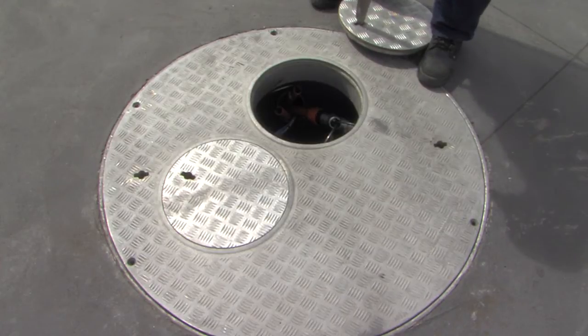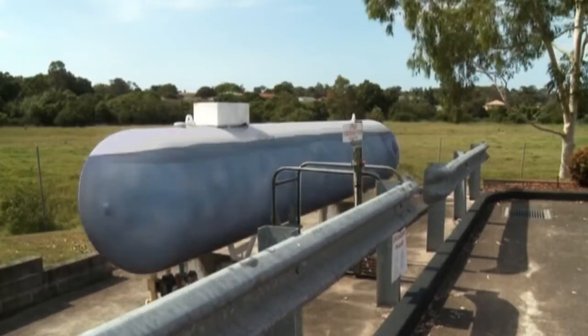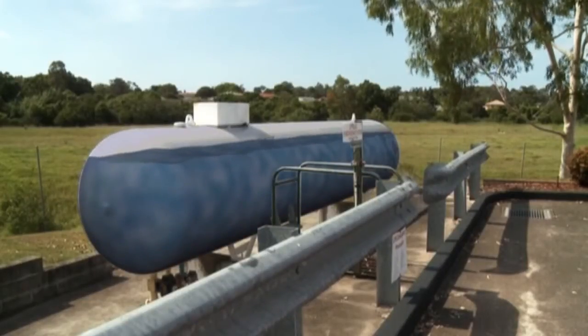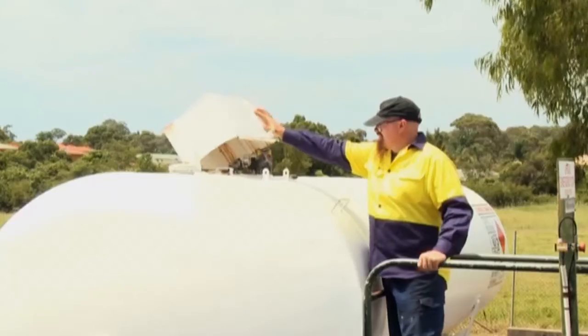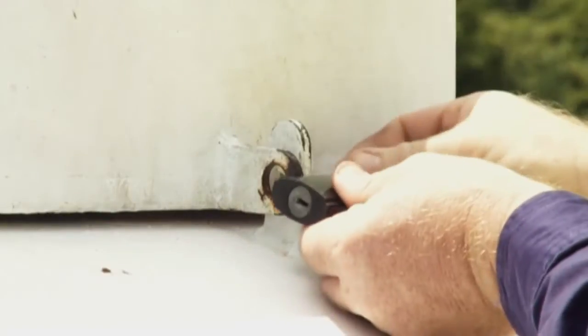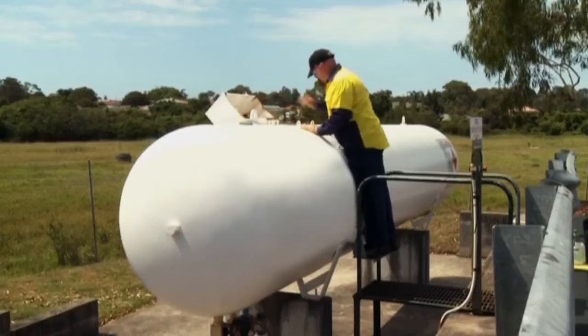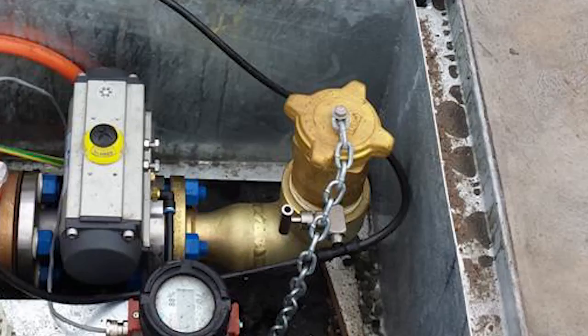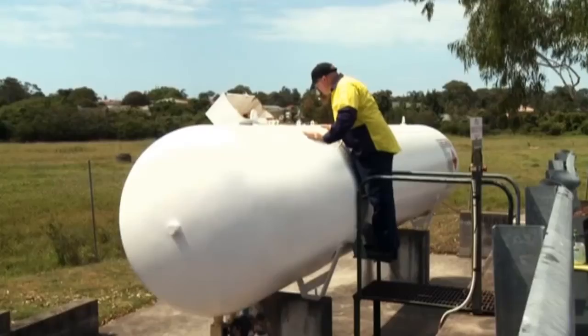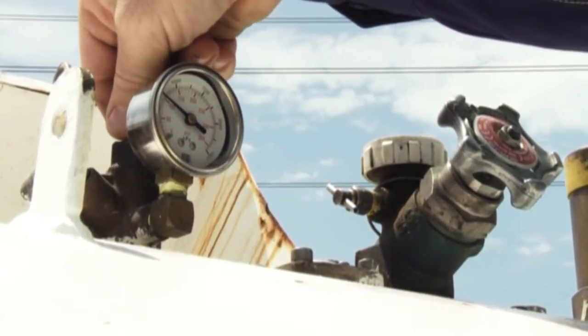System checks should include but are not limited to the following. Level gauges, pressure gauges with normal tank pressures being around 700 kilopascals or kPa. No LP gas above ground storage tank should be filled over 80 percent. However, underground LP gas storage tanks can be filled to 88 percent. Make sure that the fill point compartment is securely locked or latched to prevent tampering when not in use. Check the fill point to ensure that it is clean and secure and the seal on the valve is in its place. The access to the fill point and level gauges should be kept clear and well maintained. Ullage lines are level indicators on the bulk supply tank. Inspect for damage, for valves that are not closed and for leaks.